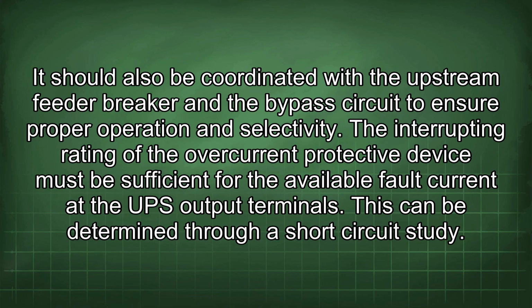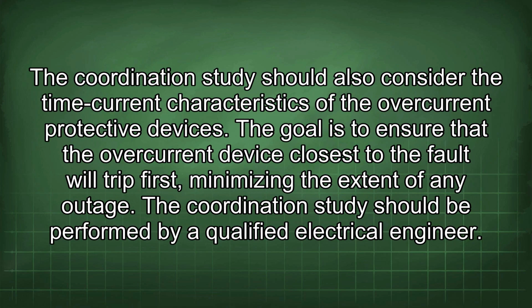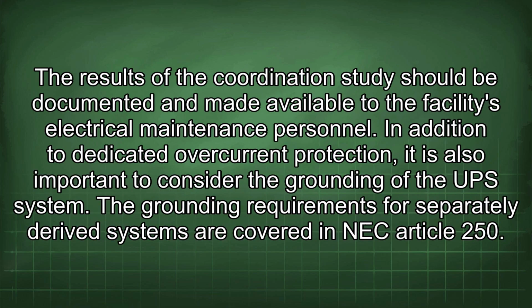The interrupting rating of the overcurrent protective device must be sufficient for the available fault current at the UPS output terminals. This can be determined through a short circuit study. The coordination study should also consider the time current characteristics of the overcurrent protective devices. The goal is to ensure that the overcurrent device closest to the fault will trip first, minimizing the extent of any outage. The coordination study should be performed by a qualified electrical engineer. The results of the coordination study should be documented and made available to the facility's electrical maintenance personnel.